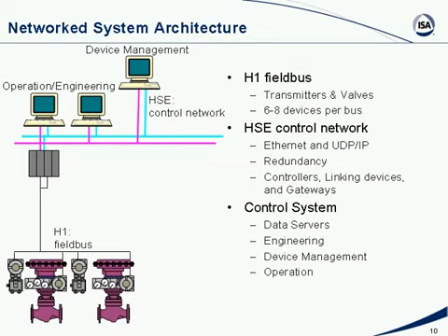At a higher level in the control system hierarchy, we have the control network. Okay, this is typically based on Ethernet media these days with TCP/IP or UDP/IP. It could be the HSE protocol, the Foundation HSE protocol, but yeah, not so many HSE devices are available. But nevertheless, Ethernet is really the media of choice for the control network in all modern control systems. At this level, at our control network, we also have redundancy, dual network, which we don't do for field bus. And control network, that's obviously where all the different controllers sit.